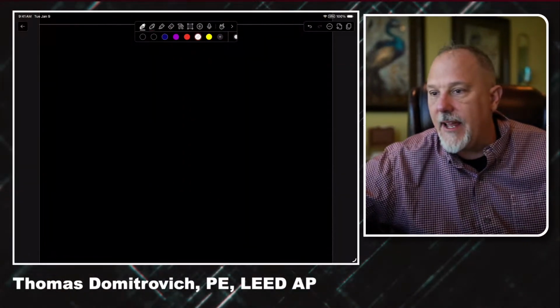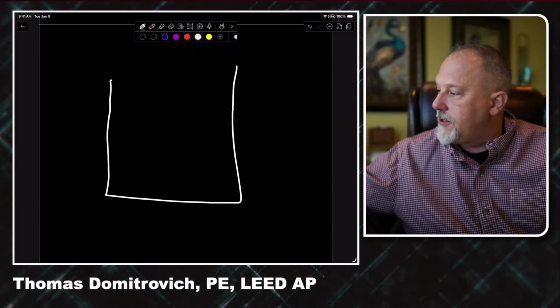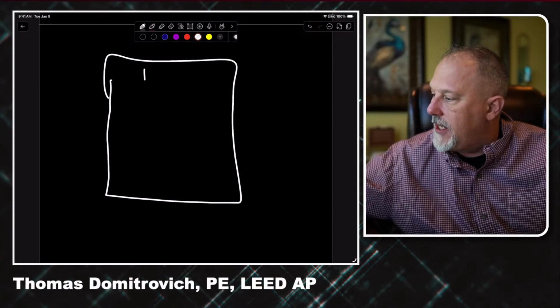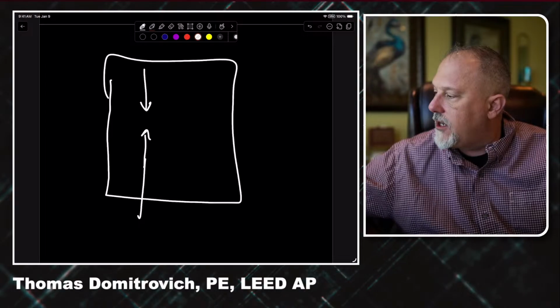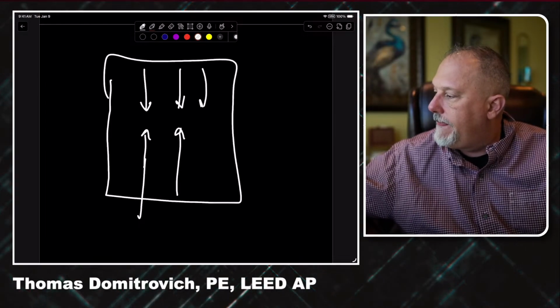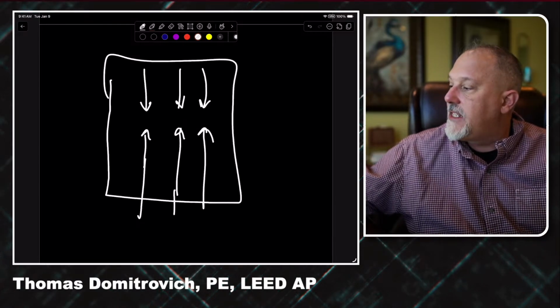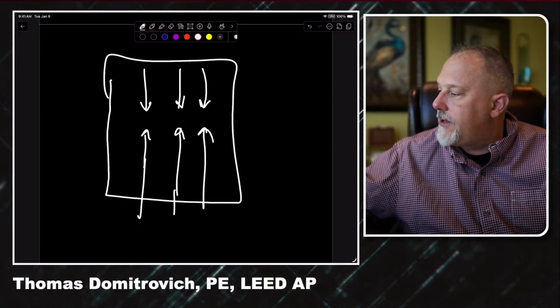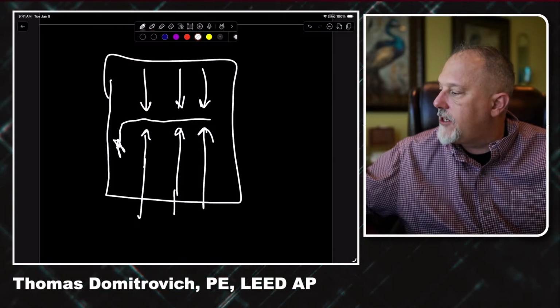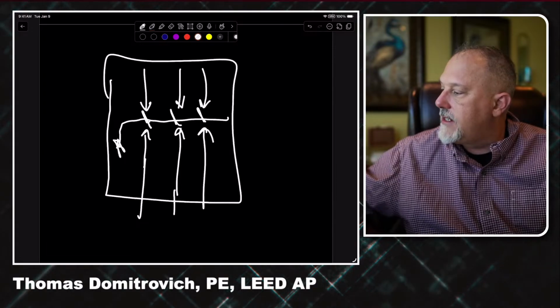And I'll tell you, some manufacturers will plot trip curves, and they'll tell you if for a single pole or a 2-pole fault, the curve is different. And the reason for that is because in some of these circuit breakers, and I'm going to do this and I have to run, when you have a mechanism, say an arm here that controls the contacts, right?